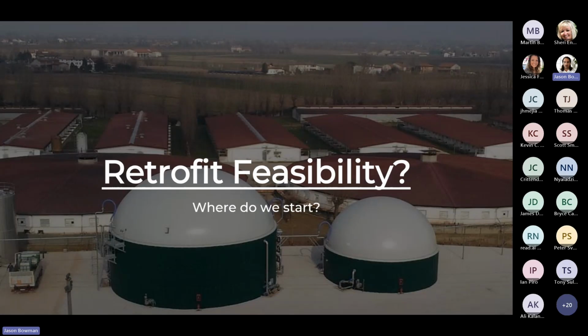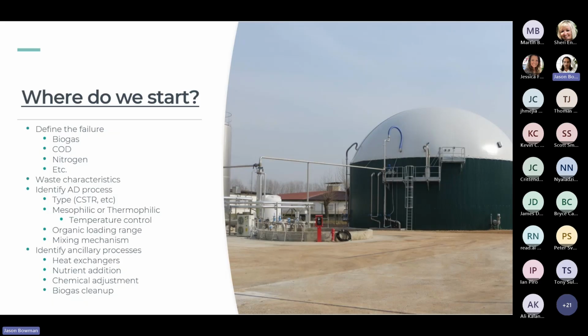So as far as retrofit feasibility, where do we start? Let's talk about how we go about evaluating how or when we can apply this technology. First and foremost, we always need to define the reason for existing system failure. Is it the loading? Is it the design basis? Is it an operational basis? Is it associated with temperature control or lack thereof?